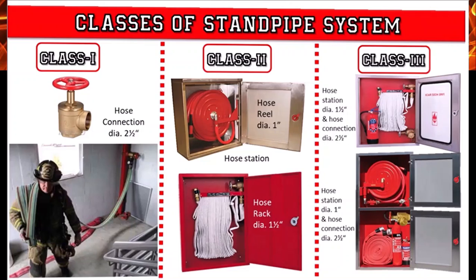Next is the Class 3 system. A hybrid of Class 1 and Class 2 systems, featuring both 2.5 inch and 1.5 inch hose connections with permanently available hoses attached to the 1.5 connections. The first Class 3 system had a 2.5 inch connection with a reducer that allowed an installed hose to be attached to a 1.5 inch connection. Firefighters removed the reducer to attach larger hoses.